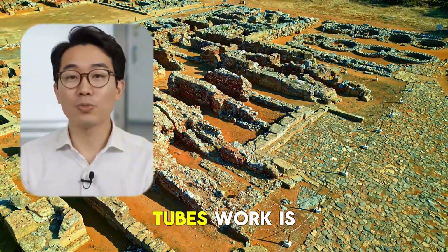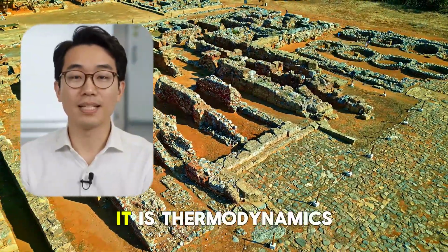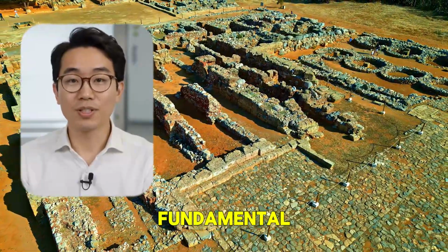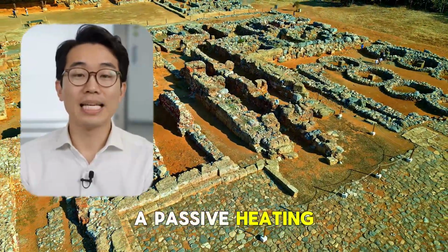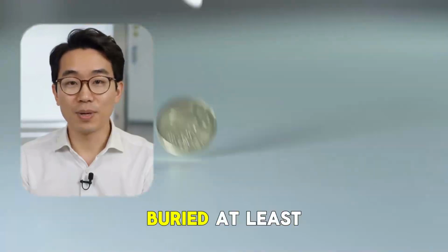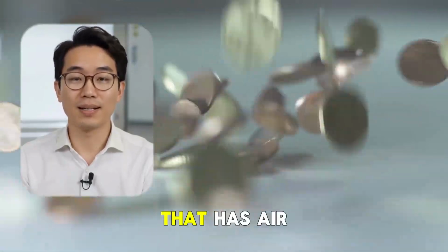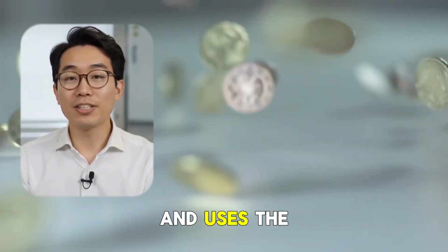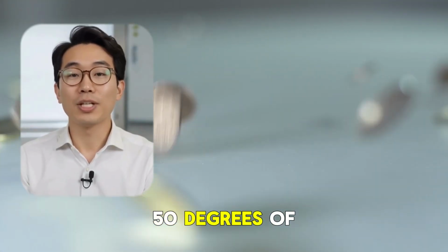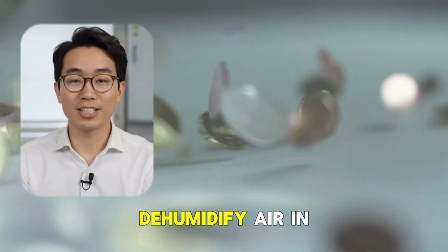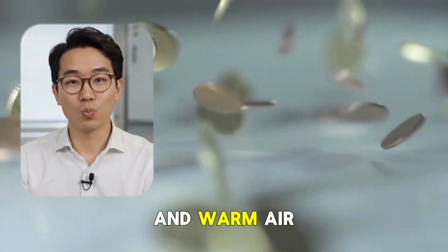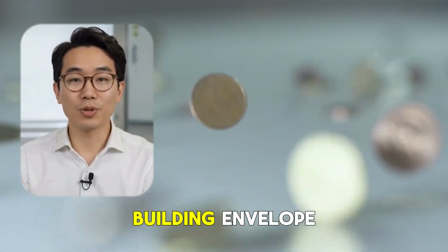The reason earth tubes work is not magic. It is thermodynamics at its most fundamental. Earth tubes are a passive heating and cooling technique that uses tubes buried at least 6 feet in the ground that has air passing through them and uses the constant temperature of 50 degrees of the earth to cool and dehumidify air in the summer and warm air in the winter before entering the building envelope.